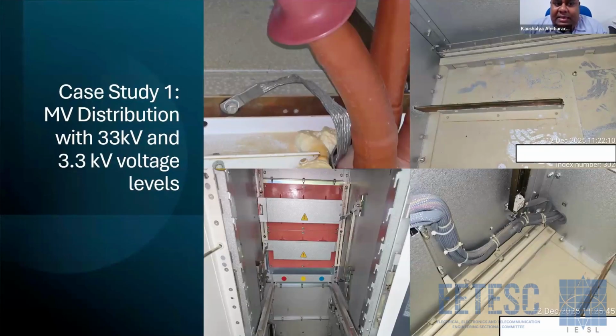An MV distribution with 33 kV and 3.3 kV voltage levels, half submerged, fully restored by the APCL staff. This was designed and installed somewhere around the mid-20s, maybe 5 to 10 years back.